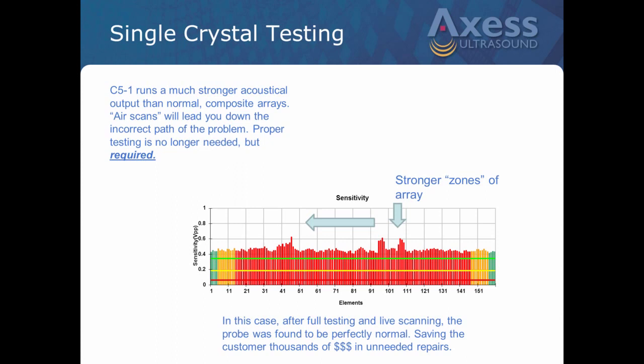And one of the things they did in the development of this, using the single crystal technology, these probes have a very strong acoustic output. They've done some other things, which I'm going to show you on lensing and so on, but it actually performs extremely well. So from a sonographer standpoint, on a thin patient or a heavy patient, they're getting good clinical images regardless using this probe. But because that acoustic output's a little bit stronger than most of your composite arrays, air scans, and this is where I'm going with testing, some of the testing methodologies that we've all used in the past just don't hold water any longer. Definitely on this probe, air scans, and we see it, will lead you down the wrong path.